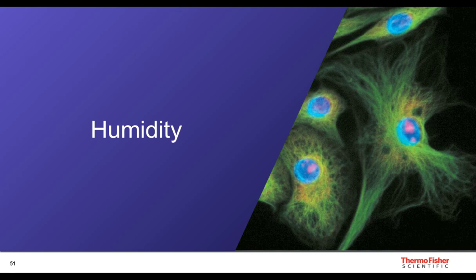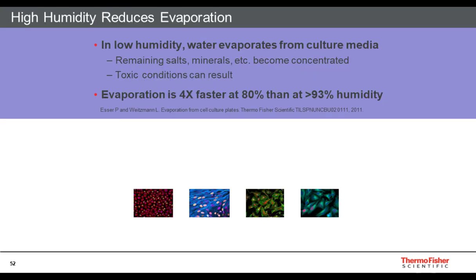Okay, so let's look at humidity. This is the last parameter of the incubator that I'm going to talk about, and it's one that's often overlooked. The reason we provide humidity in the CO2 incubator is because it reduces evaporation from the growth media. In very low humidity, you get higher evaporation. When you get evaporation, only water leaves the culture media, and as a result, the remaining salts, minerals, hormones, nutrients, etc., become concentrated, and some of those factors can reach toxic concentrations.